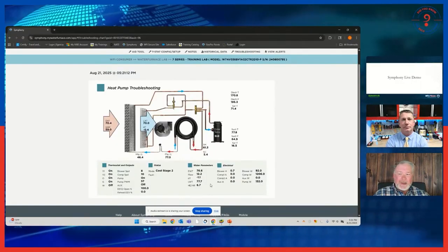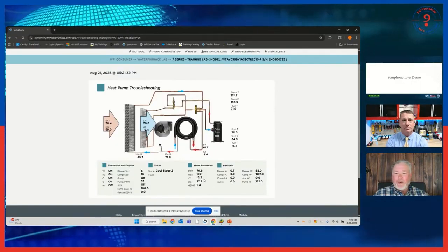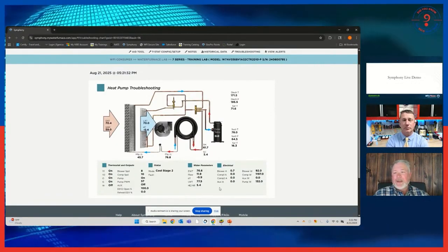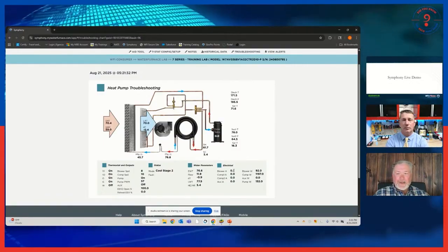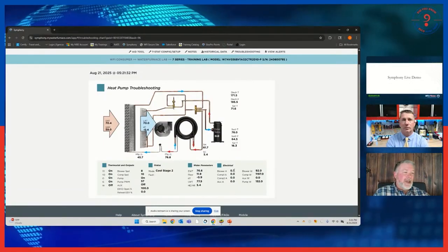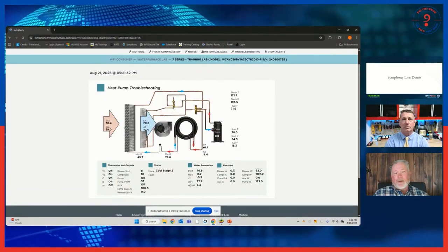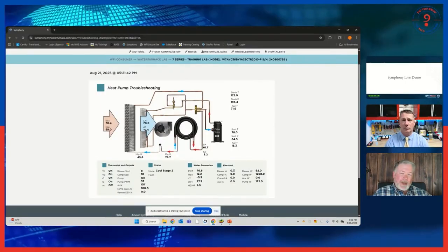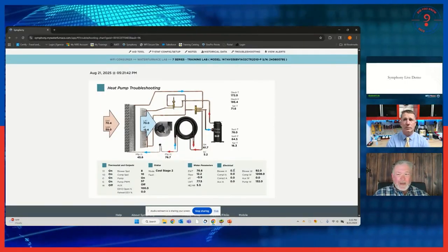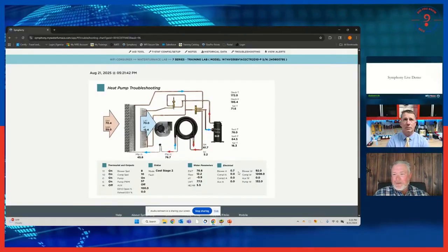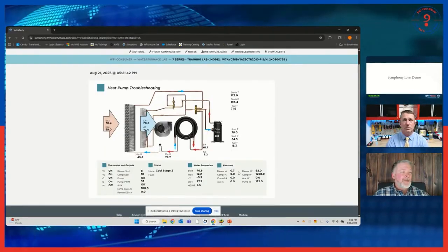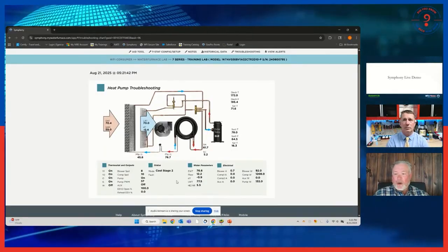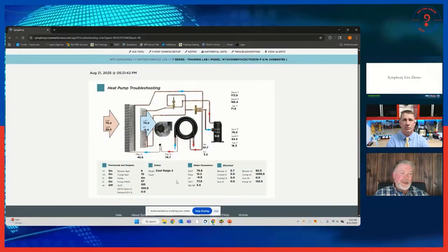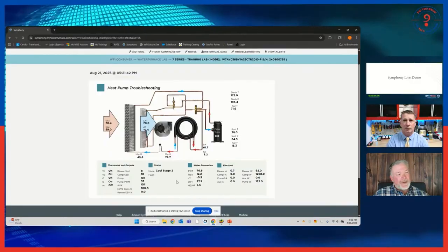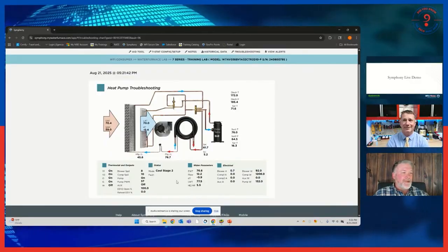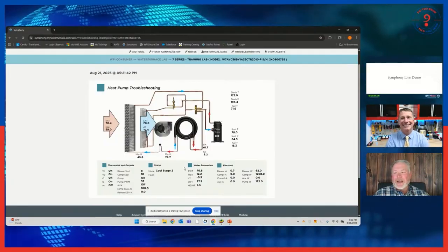On the left-hand side I've got thermostat inputs and outputs. On the right-hand side, water parameters — water flow, delta T — and electricals. So if I was diagnosing a unit that faulted out or locked out on low pressure in the middle of summer, I can check here whether my fan has any amps. If the fan doesn't have amps and there's a call coming from the board for G, maybe I should put a fan motor on the truck before sending someone out.